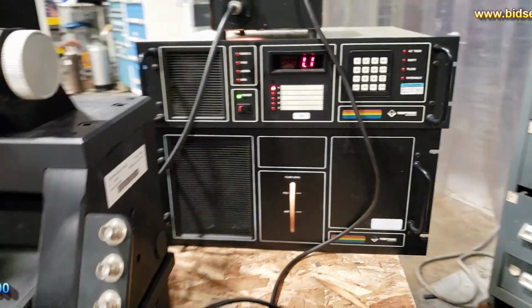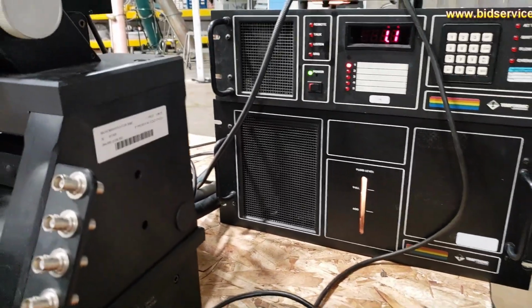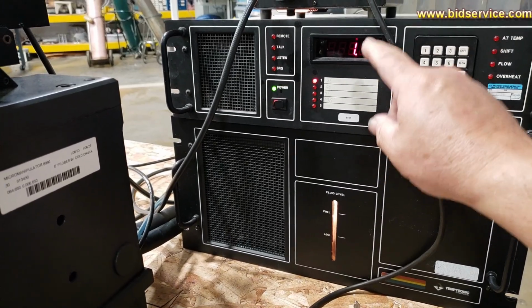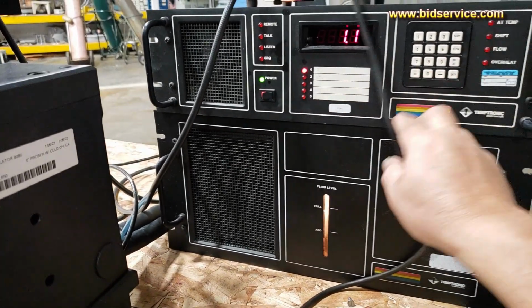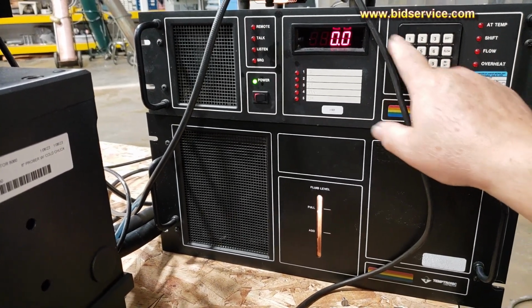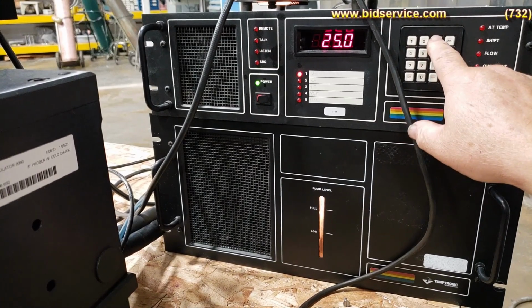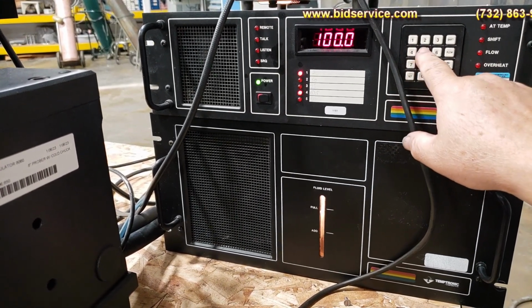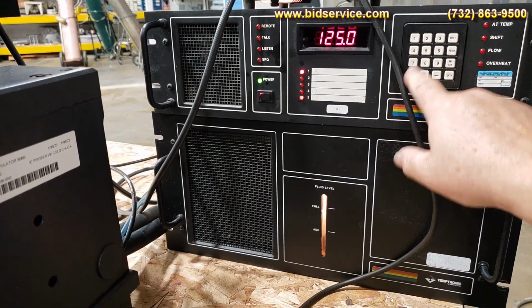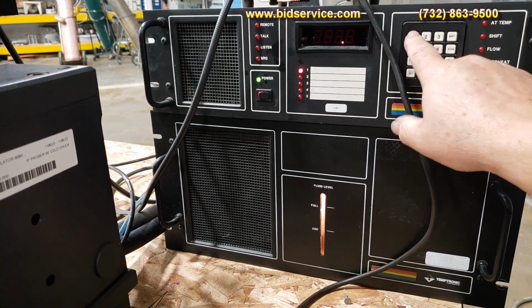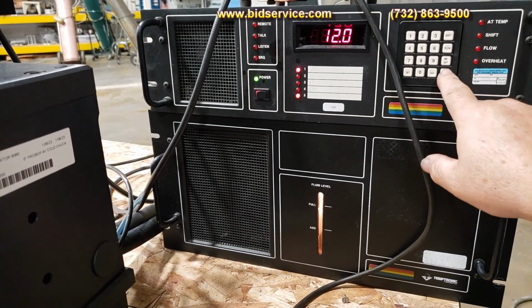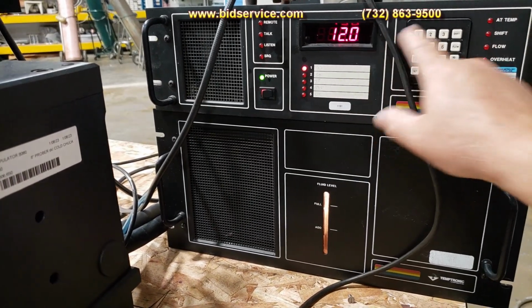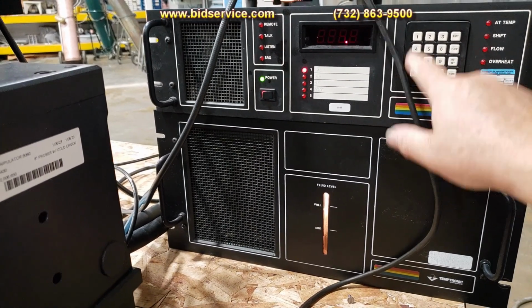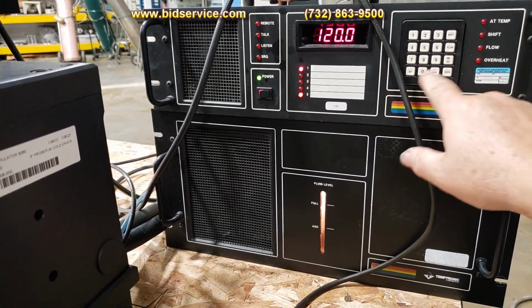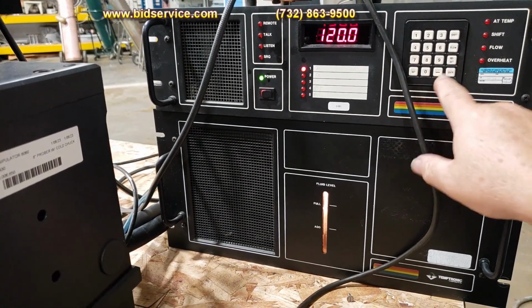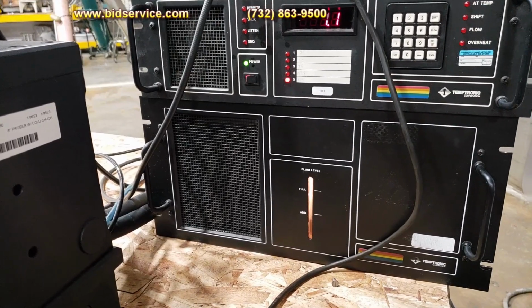Over here you have your controller for your Temptronics. For the chuck itself, it can go from 0 to 200 degrees. It has 5 different presets. To check out the presets, you can just hit a number. If that tells you it's 0, that's 2, 3, 4, and 5. If you want to change one, like if I want to change 5, you just hit set, and then you can hit whatever you want. 120. You hit enter, and if I want to go to it, I just hit 5, enter, and it will go to 120 degrees.